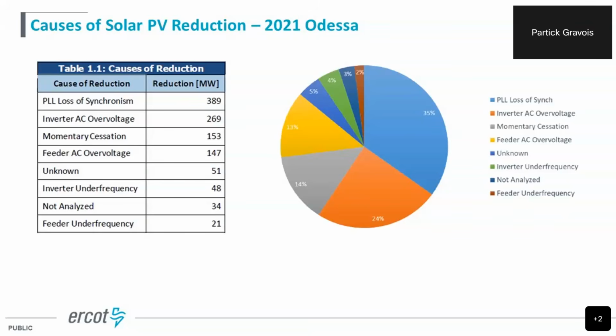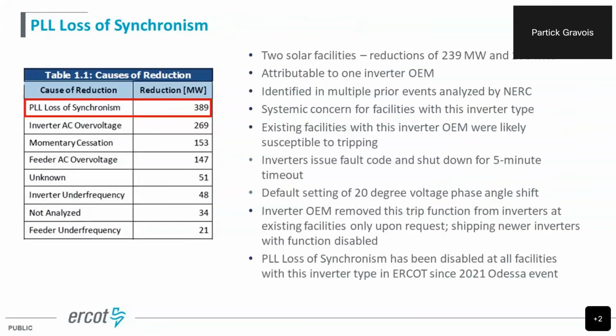But here's the breakdown. The biggest was the PLL loss of sync, and the overvoltage made over half of the losses here. So we're going to talk about each of these individually. First is the PLL loss of synchronism. There were 2 solar facilities that had reductions of 239 megawatts and 150 megawatts. This was one particular OEM. This is OEM 1, also identified in prior events analyzed by NERC. Realize this is a systemic concern with these facilities.